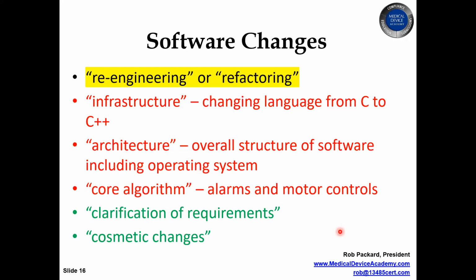And you would explain to them, maybe in an overall architecture diagram, this is where we're making the change, only this part. And these are the modules or the unit test cases that will be affected. And this is our revalidation plan. So you would actually articulate for the FDA, here's the old unit test cases, here's the new unit test cases, and these are the only ones that we're revalidating. Do you agree with this strategy?